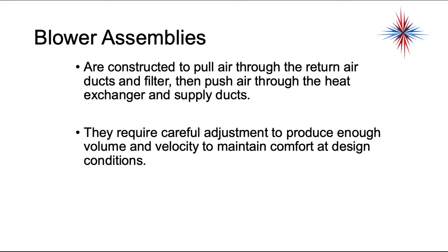Blower assemblies are constructed to pull air through the return air ducts and filter and then push the air through the heat exchanger and the supply ducts. The blower is the point of pressure change on the air side of a gas furnace. Everything on the return side of the blower is going to be a negative pressure — it's lower than the surrounding air pressure. On the other side of the blower, where we're pushing it through the heat exchanger and the supply ducts, it's in a positive pressure.